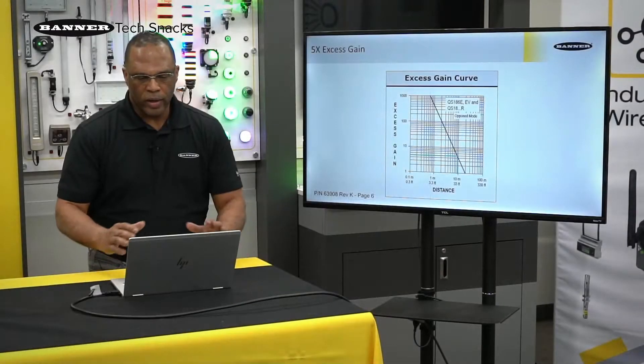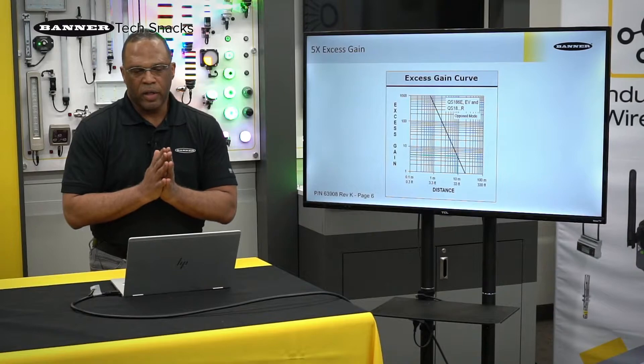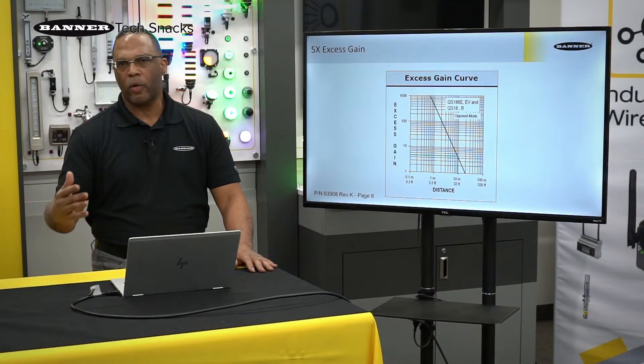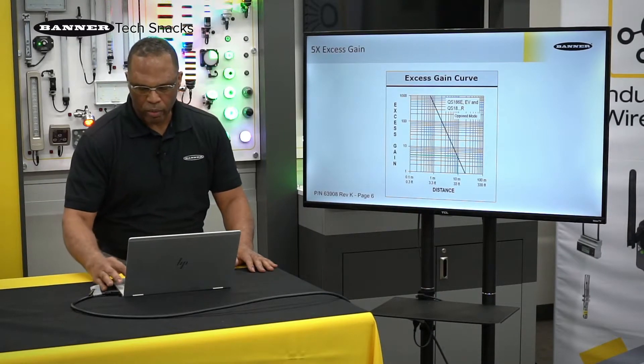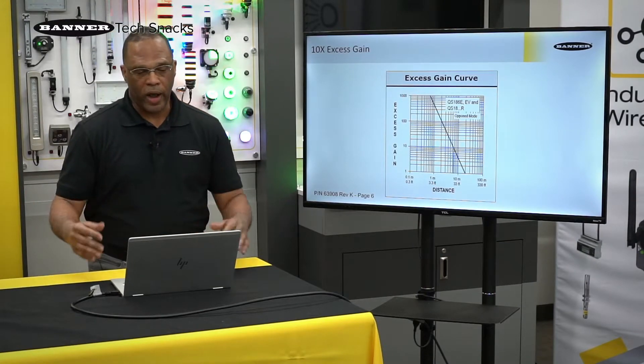Here's an example of how we would use this excess gain chart. Let's say we're in a factory and we know that dust is going to build up on the sensor. So even though this sensor can see out to 20 meters, we may not want to operate out that far. To have an excess gain of five, we really only want to be about 10 meters. Excess gain, as its name implies, is the amount of light over what is needed to turn on — only one is needed to turn on, but you don't always want to operate there. In a slightly dirtier application, you may want an excess gain of 10; the sensor can see out to 20 meters, but you may only want to be at six or seven meters to make sure you're seeing through the dust and debris. If you're in a very dirty environment and want to be at 50, you don't want to be any further than three meters back.